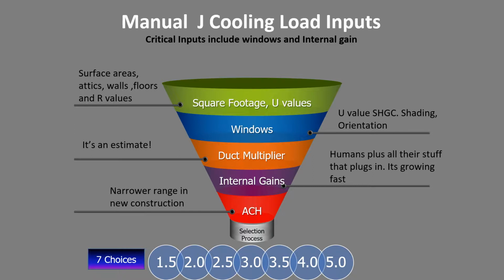Manual J cooling loads, they get a little more complicated. One, again, you need the square footage and the U values. On windows, orientation is critical, as are shading and solar heat gain coefficient. The modern window lets so much less solar radiation through than it did, say, even 15 years ago. Duct multipliers, again, all of you on the webinar today have probably been in hot attics, and we put ducts up there, and the ductwork might have 65-degree air in it, and the ductwork might be in an environment where the attic's 135 degrees. That's a pretty big delta T. So yes, you're going to hear us talk about the importance of at least looking at the duct system today. The internal gains, that's all the humans and the stuff that they plug into the wall.